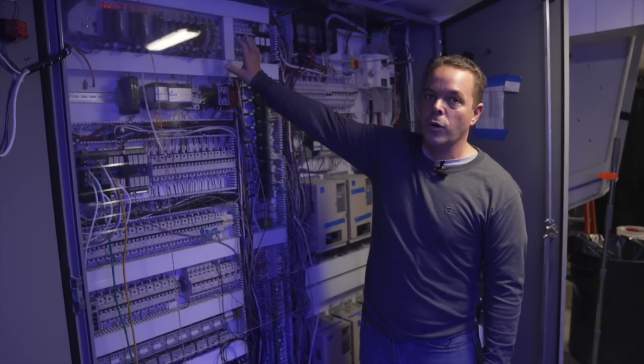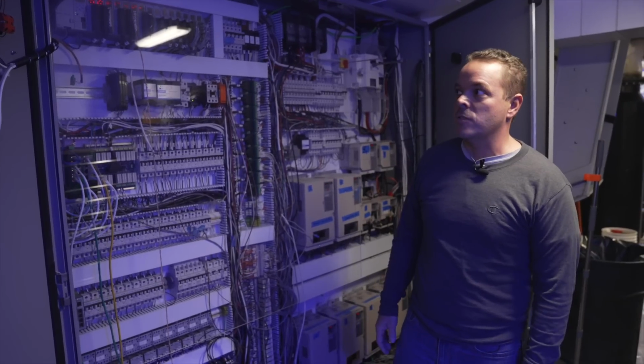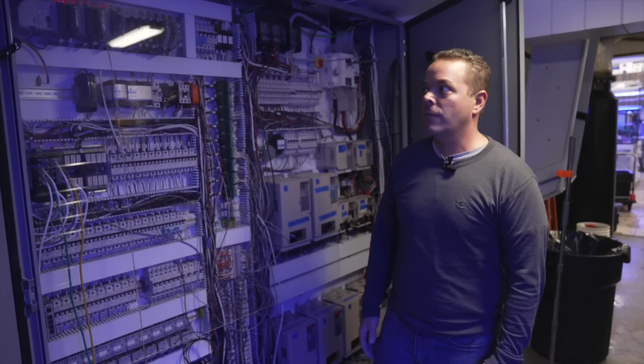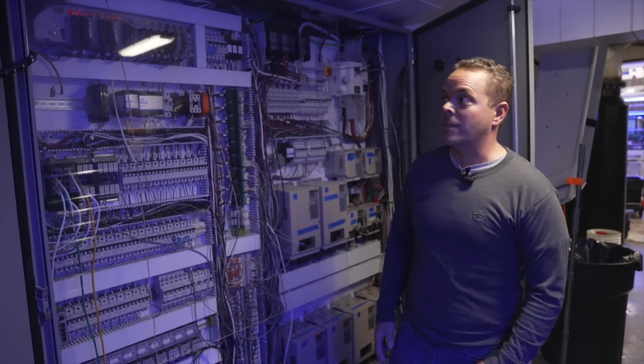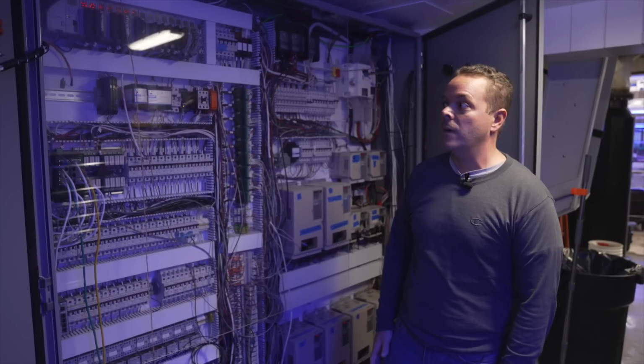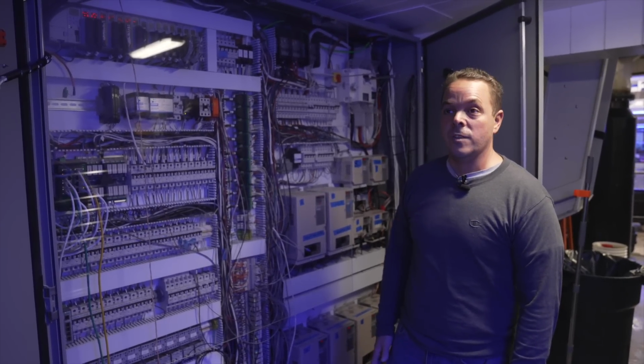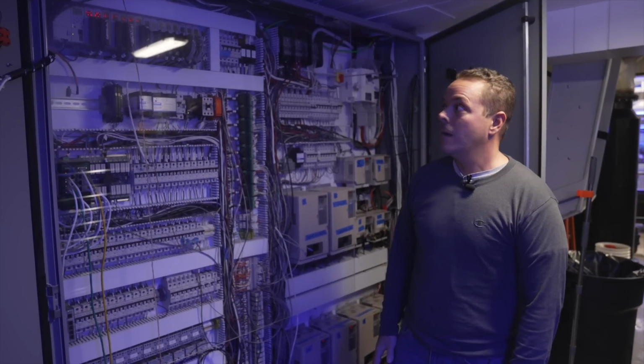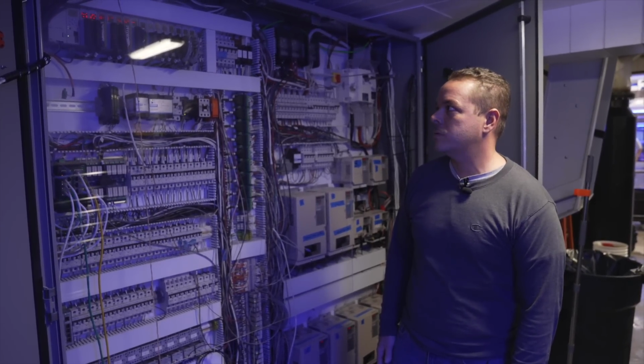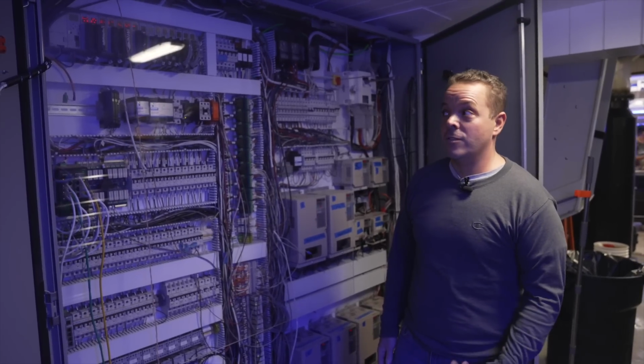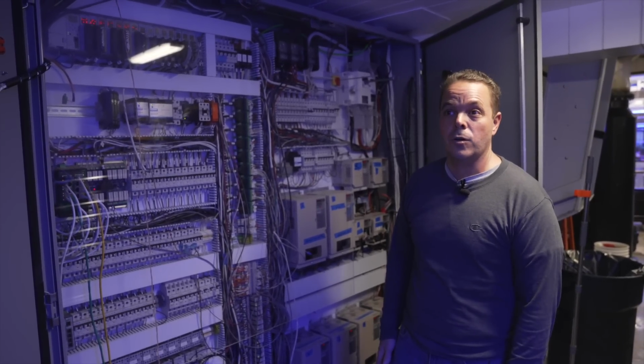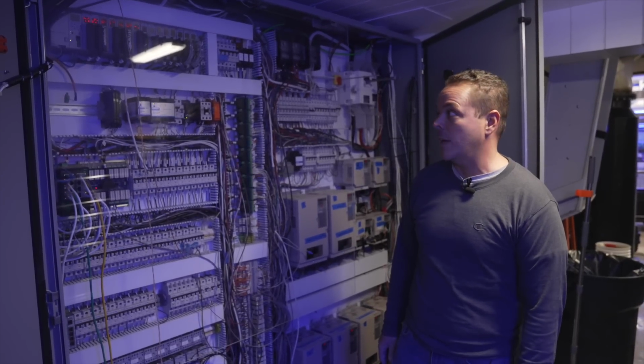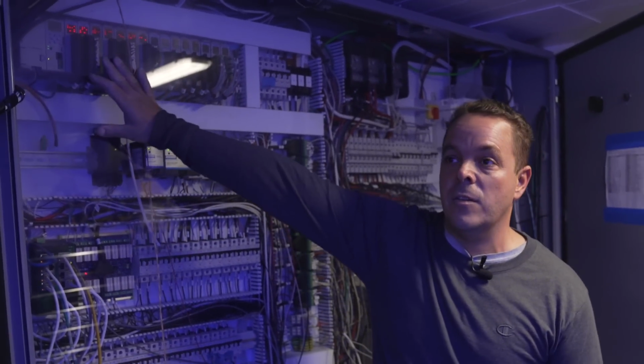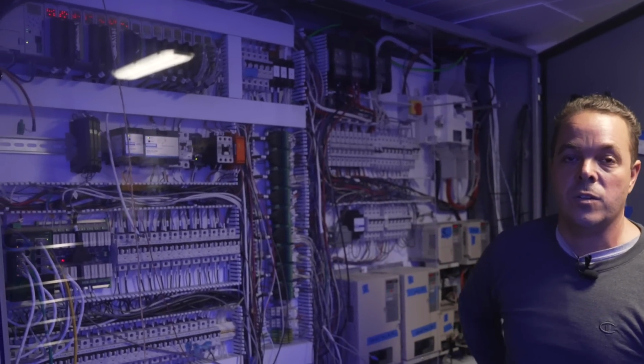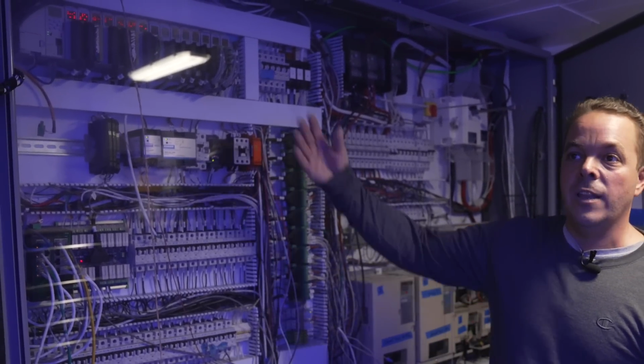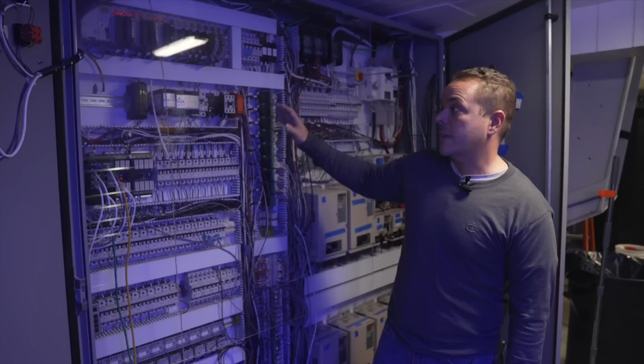We have the PLC portion, which would be equivalent to like an Apex, but this is more commercial automation, or for like factories and things like that. It's able to process data at a tremendous speed. It actually scans all its sensors multiple times per second. How many probes do they have on this system, running all the pipes and stuff? Between flow sensors, temperature, all of those, you probably have 50, 60 probes in different locations with different applications. All the inputs are into here, and there's a brain, and there's actually 2 remote locations downstairs where there are separate standalone units that all relay their information back to here. So there's countless data points from that.